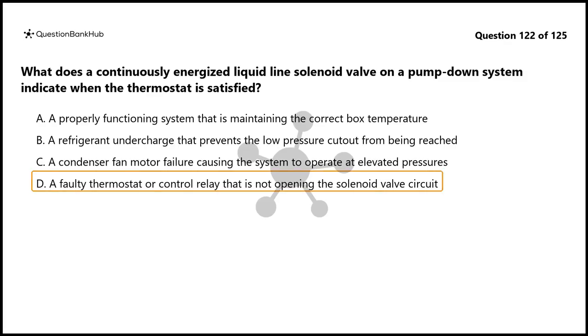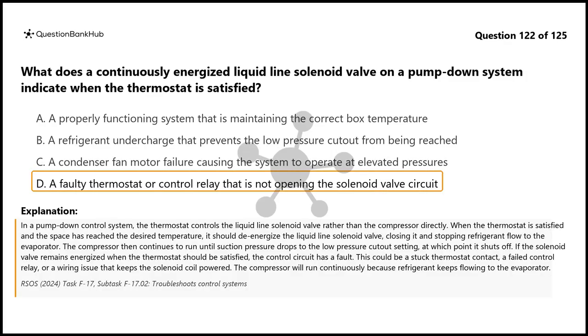The correct answer is D. In a pump-down control system, the thermostat controls the liquid line solenoid valve rather than the compressor directly. When the thermostat is satisfied and the space has reached the desired temperature, it should de-energize the liquid line solenoid valve, closing it and stopping refrigerant flow to the evaporator.